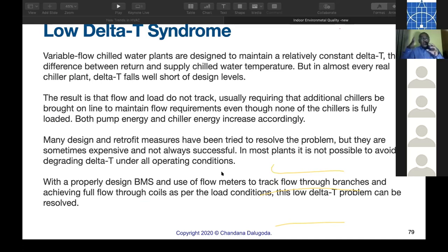You will require additional chillers brought online. Oh God. The AHUs are not loading, may sometimes not be achieving temperatures, but still we have to load another chiller because our flows are not correct. Additional chillers are brought online to maintain flow requirements, even though none of the chillers is fully loaded. Both pump energy and chiller energy are increased accordingly.